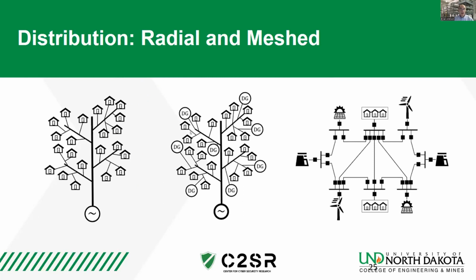Now, when I talk about having these connections, for example, if we look at the system from here to here, we may have a connection between these two. We have a switch that's normally open. And then if there is a short circuit on this part of the system, we would open a switch here and close that switch, and we could feed the end of this feeder from this. When utilities have had these connections for a long time, originally they would basically roll a truck and have a human go out and make these connection changes.